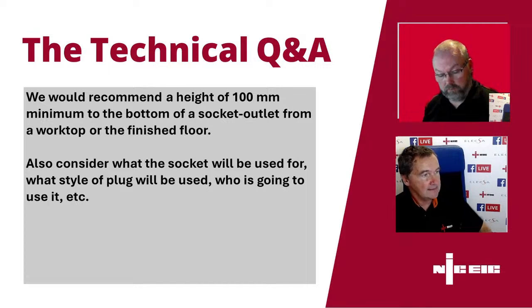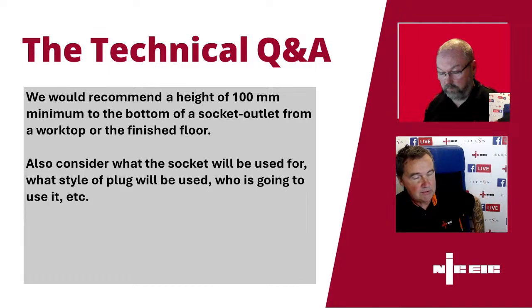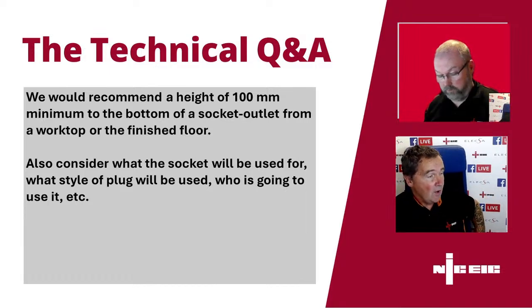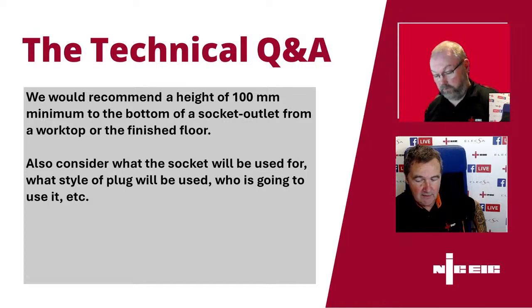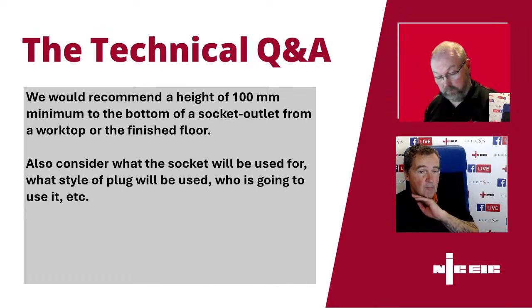So yeah, there's no issues with the bottom. You might find issues with other trades afterwards, if it's the bottom that they're going to be fitting their ceiling onto. But as far as 7671 is concerned, and protection of the cable and maintaining the structural integrity, so that you meet the requirements of Part A of the building regs, there's nothing to suggest that you can't notch the bottom.